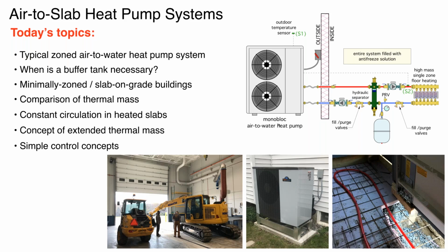I feel it applies very well in garage type buildings where you have these large overhead doors like you see down at the bottom of the screen there. Those are the areas that cool off faster when flow stops. And they tend to be cool spots, and in extreme conditions, they can also be areas that will potentially freeze. If it's extremely cold and there's no flow and it's just water in the circuit, that's where freezing is going to start. So we're going to mix in constant circulation to the discussion.